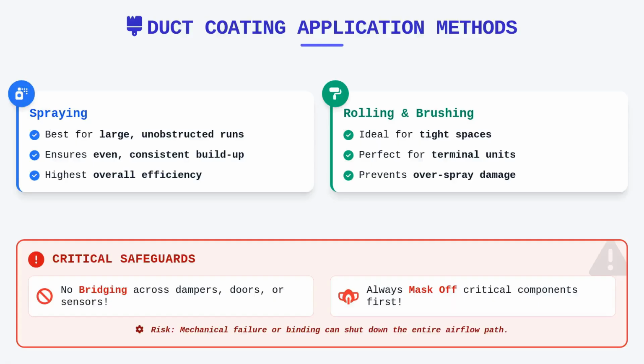The methods of application vary depending on the geometry of the duct and the specific properties of the coating being used. Spraying is generally the most efficient method for large, unobstructed runs of ductwork, allowing for an even, consistent buildup of the coating across the interior surface. In contrast, rolling or brushing is more appropriate for tight spaces, terminal units, or areas where overspray could inadvertently damage sensitive components. Regardless of the method, you must be hyper-vigilant about the physical operation of the system.